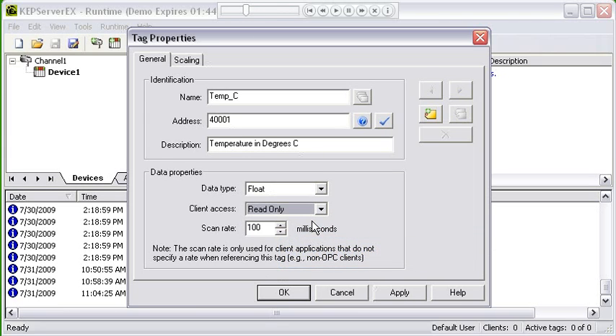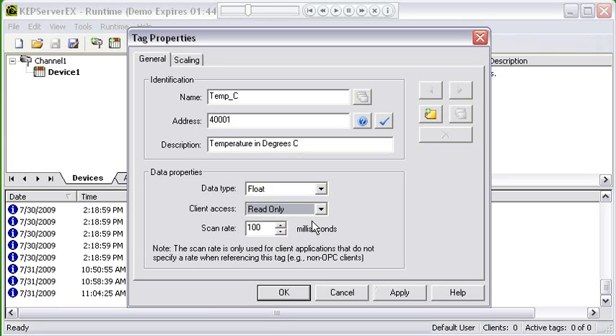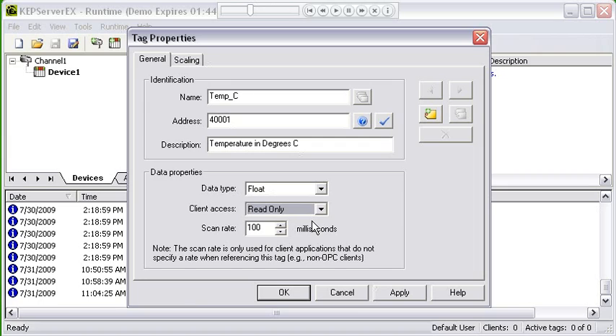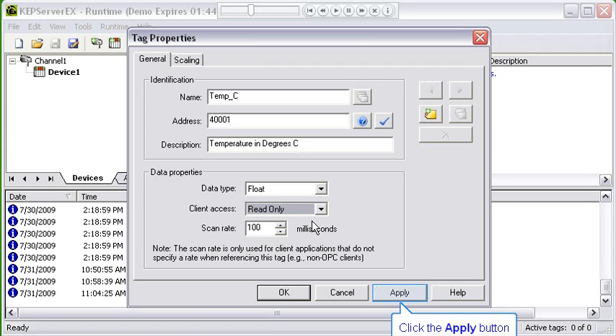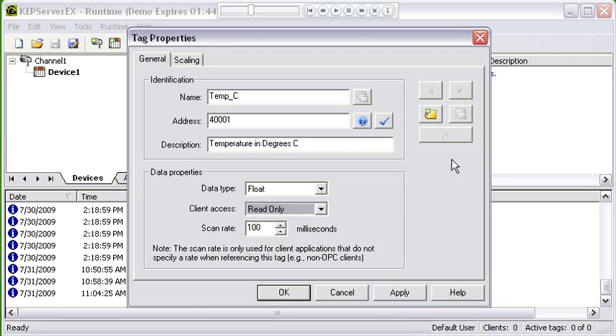The last piece here in data properties is the scan rate. The scan rate is for non-OPC clients. If you're connecting with Excel or Wonderware or GE's iFix, these all have native interfaces. For Excel it's DDE, for Wonderware it's Fast DDE Suite Link, for iFix it's PDB and IO. These don't do OPC requests and responses, so there's no scan rate passed to the server when they connect. They use this scan rate that's set here to pull the data for this address. I'm going to apply this.